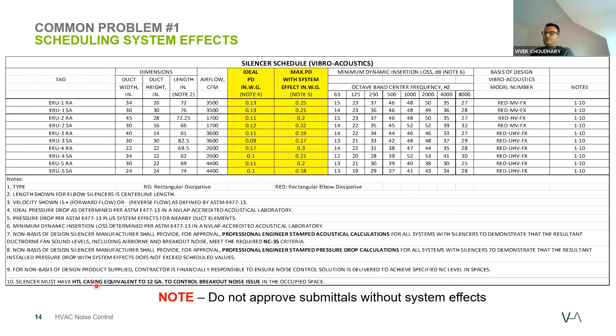We also put some notes here, which any consultant looking into the project can review. Basically, we are providing all the calcs needed for that project to provide you the background on the job, what Vibro-Acoustics and Long have done. And also we provide PE stamp pressure drop calculations as well. The last note here says silencer must have an HTL casing to control the breakout noise issue. That actually comes to the common problem number 2, which is breakout noise.